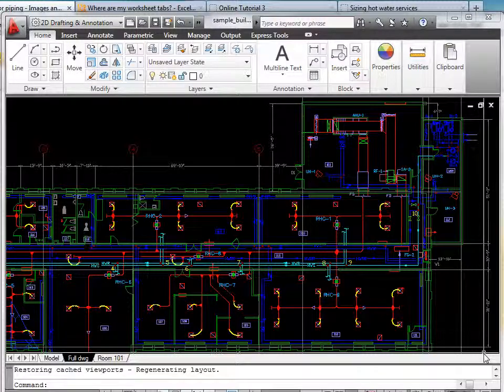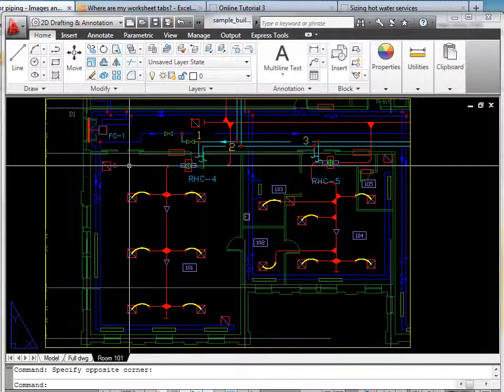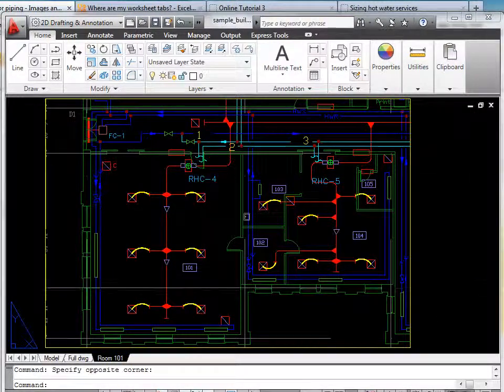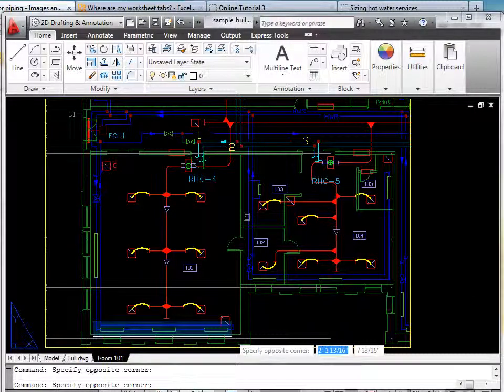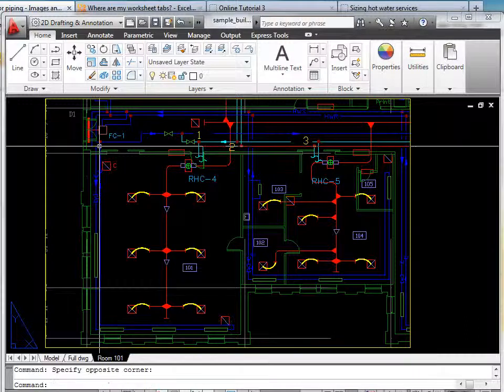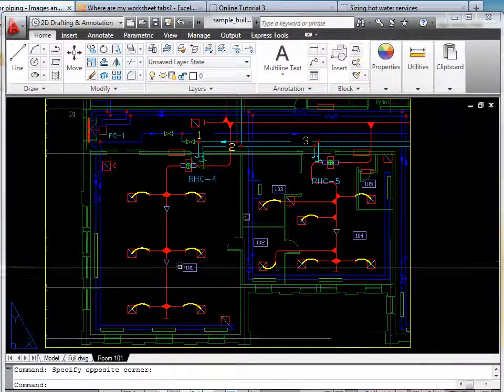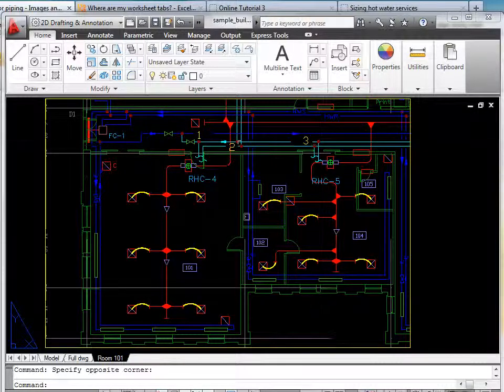Prior to pipe sizing, the piping network layout, shown for the sample building by blue and cyan lines, has to be developed, and the heating loads of the baseboards and reheat coils calculated, as it was discussed in Tutorial 2. The space comfort for assembly room 101 is provided by the air supply duct with 6 diffusers, reheat coil RHC4, and the baseboards located under the windows. The blue lines of piping distribute hot water to the baseboard, and the lines shown in cyan color represent the piping serving the reheat coil.